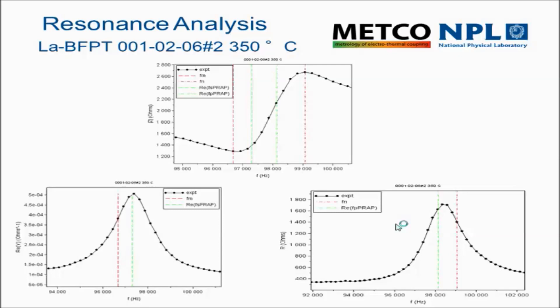There's another, more subtle effect. In this top graph, showing the resonance spectrum expanded around the resonance area, the red lines are the maximum and minimum of the modulus of the impedance as described in the standard. But the green lines are the series and parallel frequencies — two of the frequencies specified and used in PRAP. In a low-loss or no-loss material, all of these frequency pairs are equivalent and these two pairs of lines should coincide. But in fact they don't — and they don't by quite a long way. That is one of the major sources of error when using the modulus of the impedance as described in the standard.